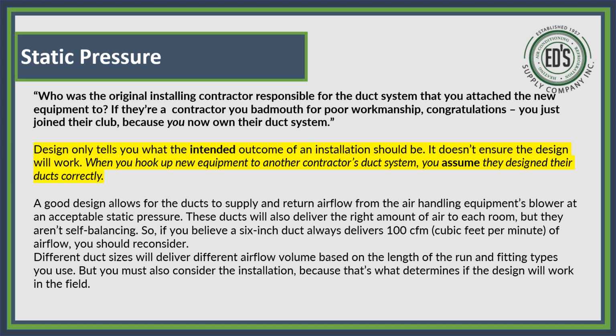A good design allows for ducts to supply and return airflow from the air handler's equipment blower at an acceptable static pressure. These ducts will also deliver the right amount of air to each room, but they aren't self-balancing. So if you believe a 6-inch duct always carries 100 CFMs of airflow, then you should reconsider. Different duct sizes will deliver different airflow volumes based on the length of the run and fitting types you use. You must also consider the installation because that's what determines if the design will work in the field.